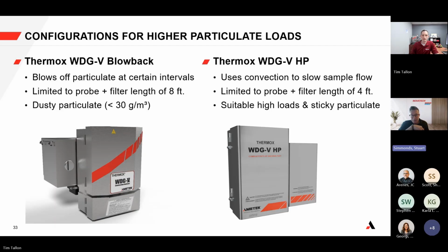But that said, the HP always has a filter on the end of our probe, correct? Yeah, HP does, same with the blowback. The other nuance is I want to make the distinction between some particulate, high particulate, and extremely high particulate—those are the buckets I think about if there's a concern.